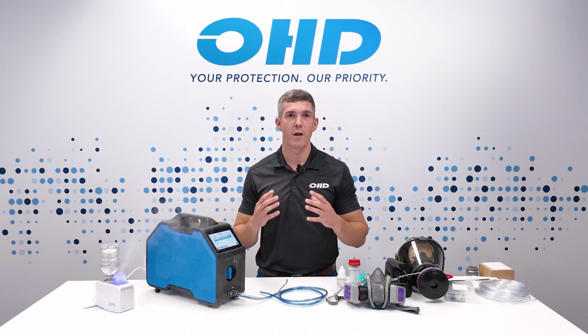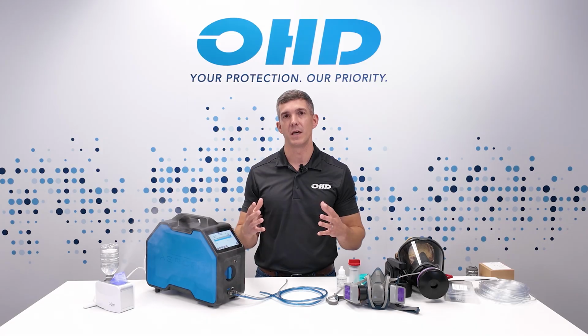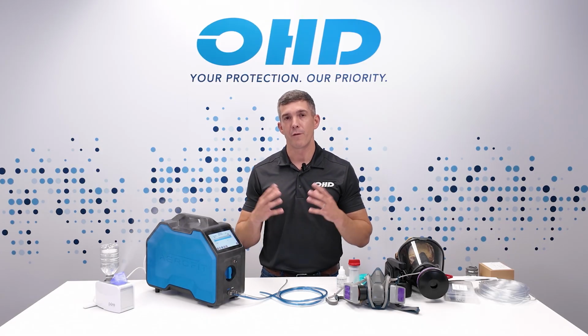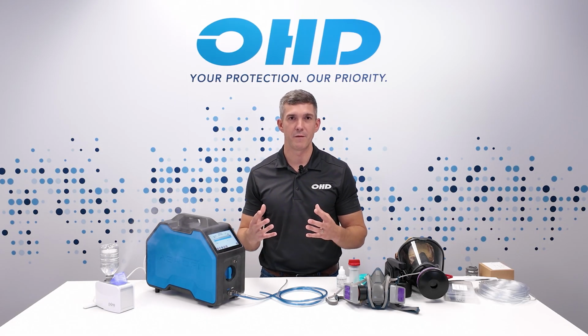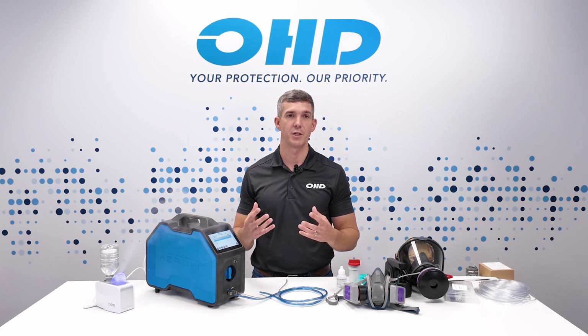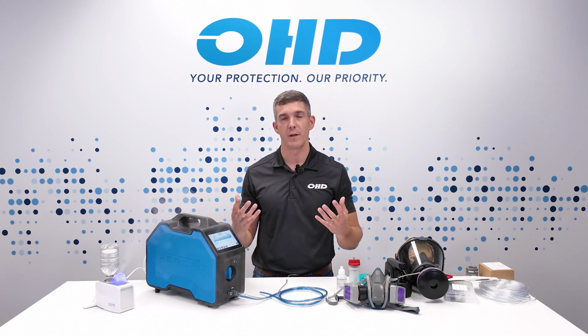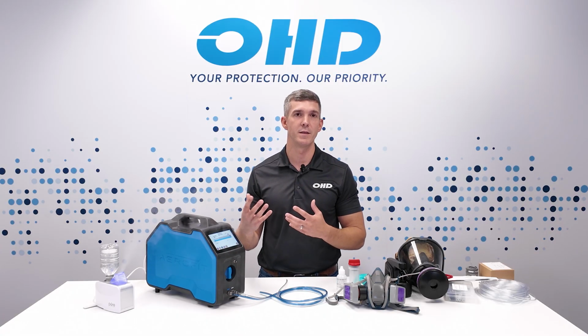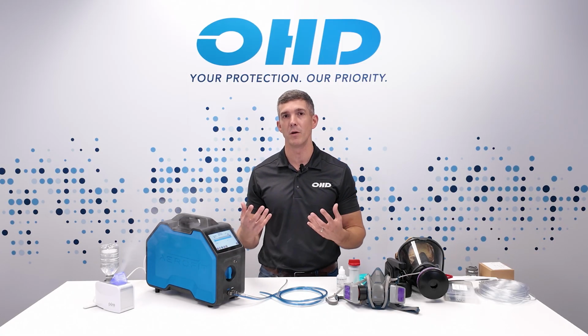Troubleshooting fit testing with your AeroFit system has a number of steps that are important to remember. The first most common issue with CNC fit testing is particle concentration in a room. So really you have two different issues here. Number one is not enough particles. That's probably the most common.